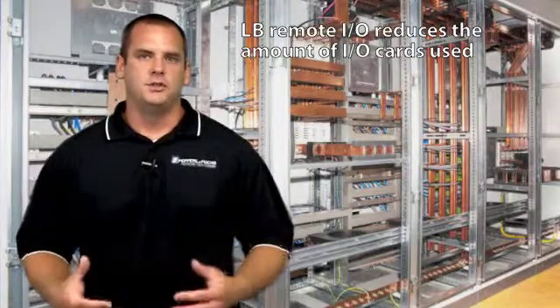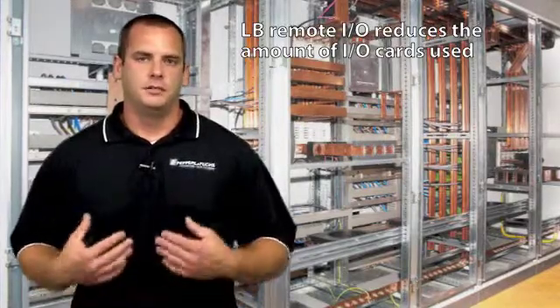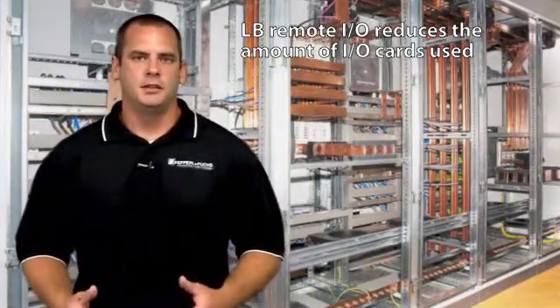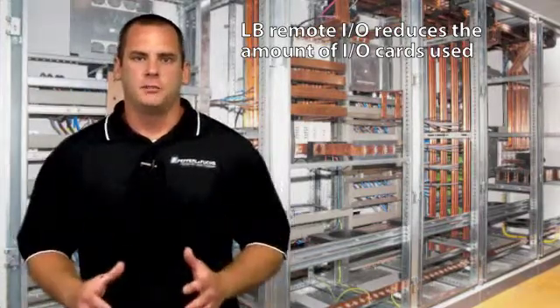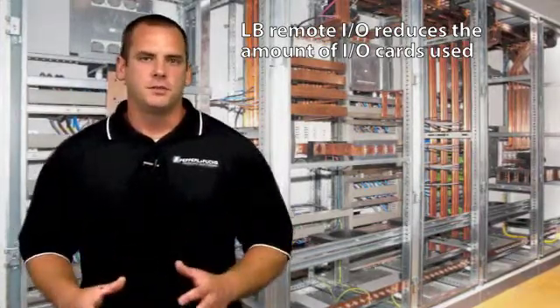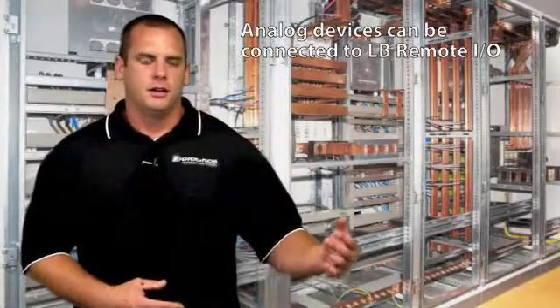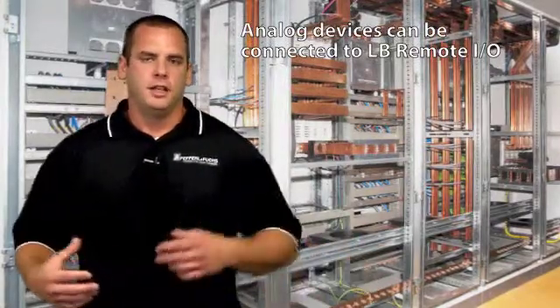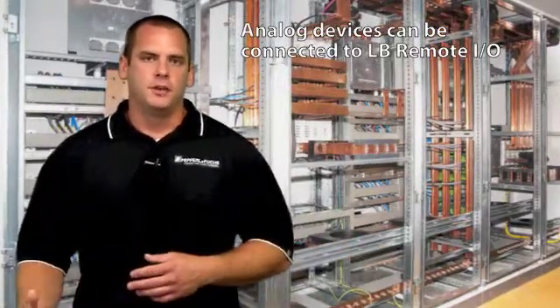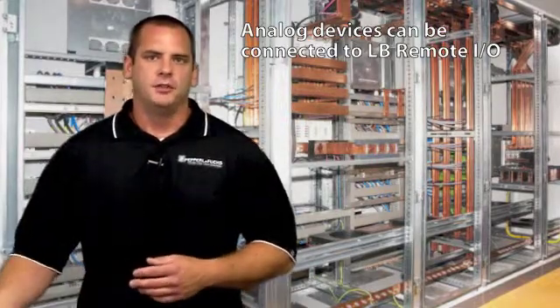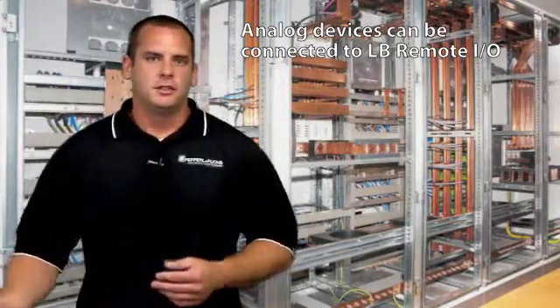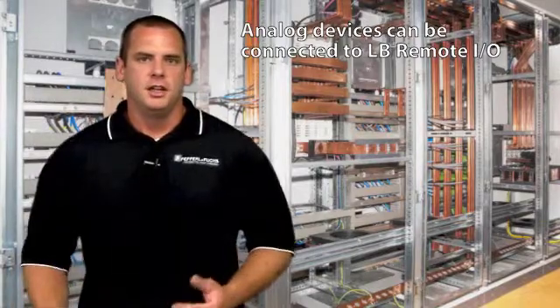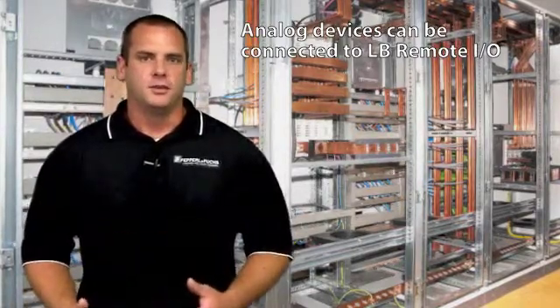The advantages of this are now you can eliminate or reduce the number of I.O. cards you need in your DCS cabinet, which is going to in turn make your cabinet smaller, using up less real estate and saving you money. Another advantage is if you have a device that doesn't have a field bus interface, you can then connect that into the Remote I.O. system and put that onto a digital bus. The digital bus gives you more robust communication and more reliable information back to the controller.